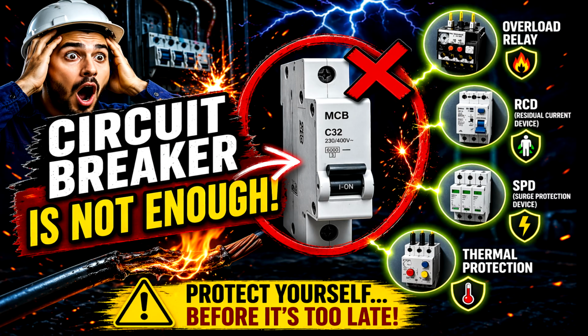Types of additional protection you must have. So we said the breaker alone is not enough. What's the real solution? You need additional protection systems. This is what separates basic work from professional electrical design. First type, overload relay. It works on a simple principle. If current increases gradually above normal, it won't trip immediately. It waits for a time depending on the overload level. Why? To distinguish between temporary normal load and dangerous overload.